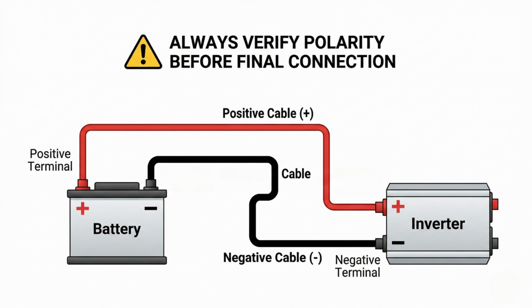Here is a practical example. A 2,000-watt inverter on a 12-volt system can draw close to 200 amps. That is a serious amount of current. Depending on the cable run, you may need heavy cable like 2-aught or even 4-aught to do that safely. The key takeaway is simple. Always size your wire based on maximum current draw, total cable length, and acceptable voltage drop. Not average use, not guesswork, not what a cable looks like in your hand. And if you are ever unsure, sizing up is usually the safer decision.